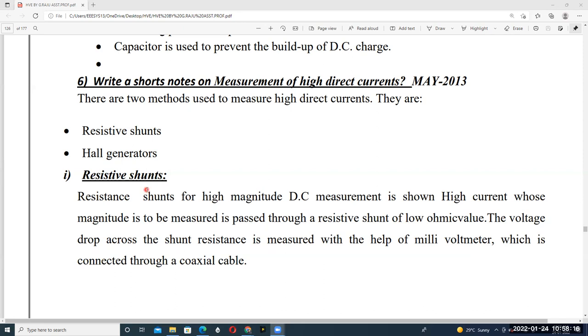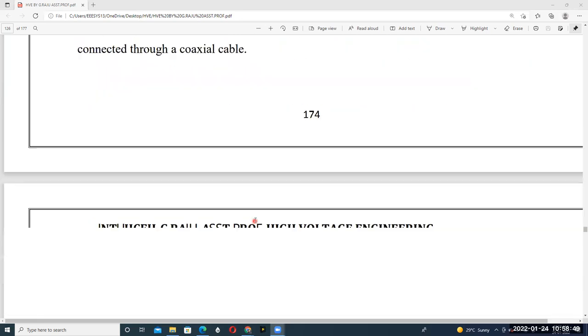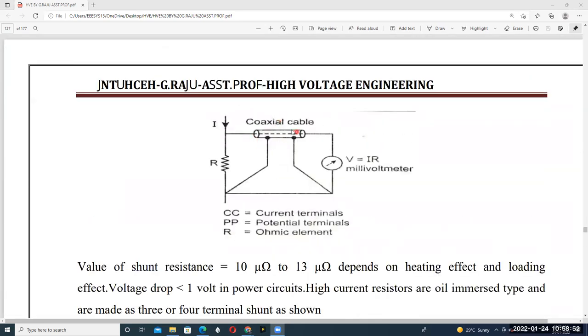The resistance shunt, for high magnitude DC current — the high current whose magnitude is to be measured — passes through the shunt. This low ohmic value resistance (the shunt) is connected in parallel to the basic meter. The voltage drop across the shunt resistance is measured with the help of a millivolt meter connected via coaxial cable.